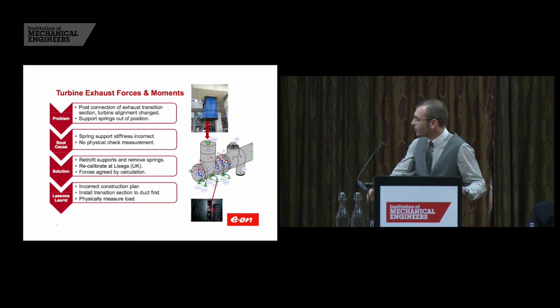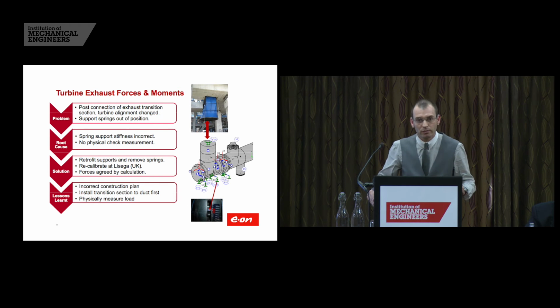So what did we do to rectify this? We welded supports below the air-cooled condenser duct, removed the spring pots, took them down to Lisega, recalibrated them and reinstalled them. However, we needed to prove to the turbine manufacturer that the forces on the steam turbine had not been exceeded. This was not able to be done by physical measurement, and we had to do this solely by calculation. What can we learn from this?